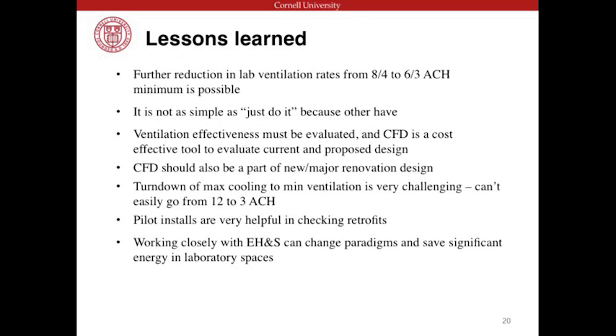One of the things we found was that sometimes you have to change out the VAV boxes, those variable air volume control boxes, because in original designs they were oversized. So to get from the max cooling level down to the min level, you're below that 30% min level, and it makes it hard to control. So sometimes you have to resize the VAV boxes, so you have to pay close attention to that.